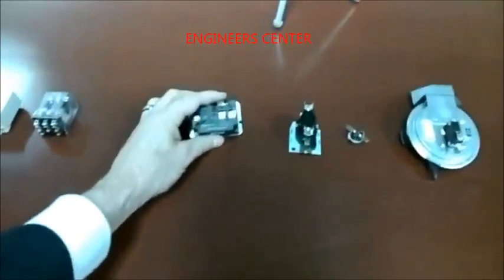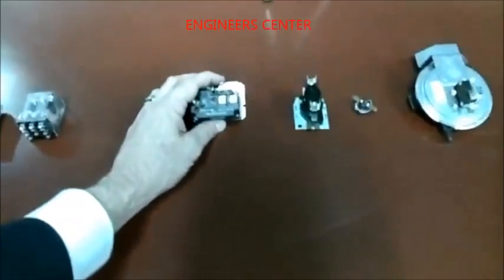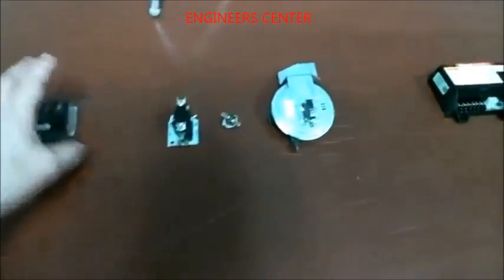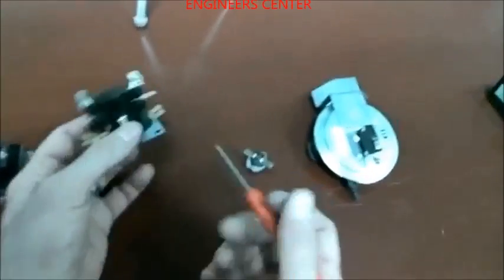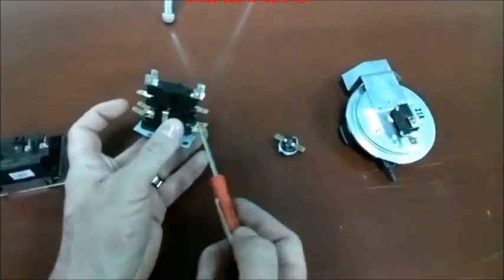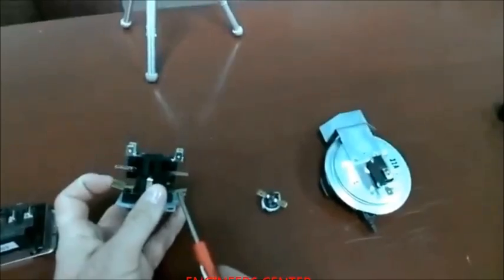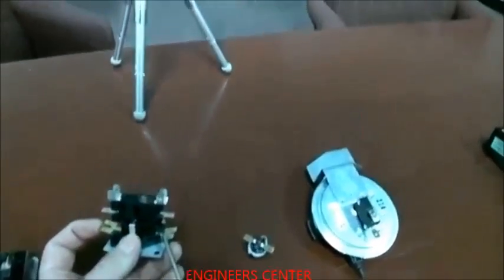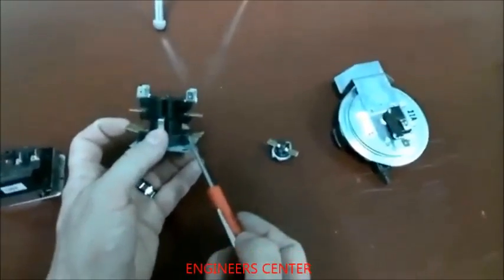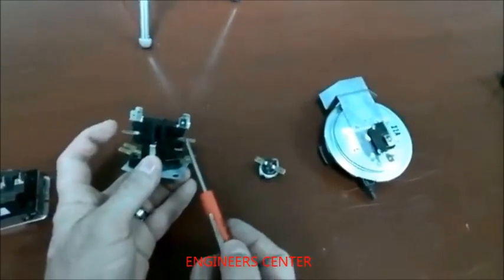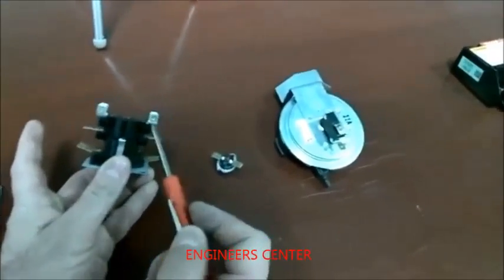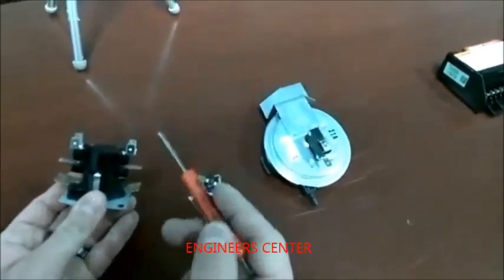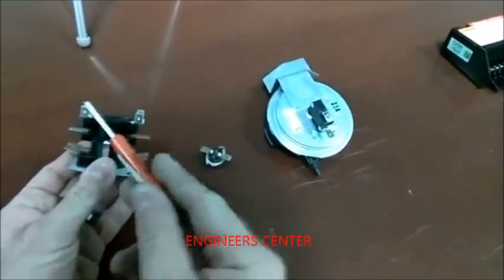And so if you were to troubleshoot that, you would give it power, see if it closes after its time delay. Same here. We have another time delay relay, a double stack sequencer. And so you give 24 volts to the bottom here, and the disk starts warming, and after a second, this one will close to there, and then after another second, that one will close to there.